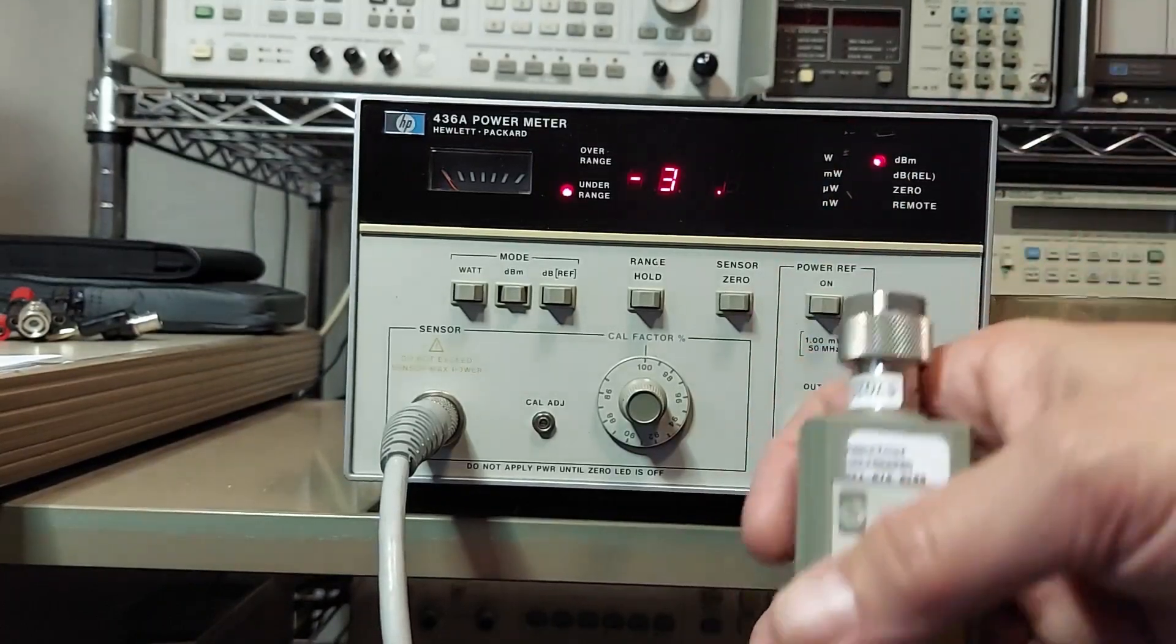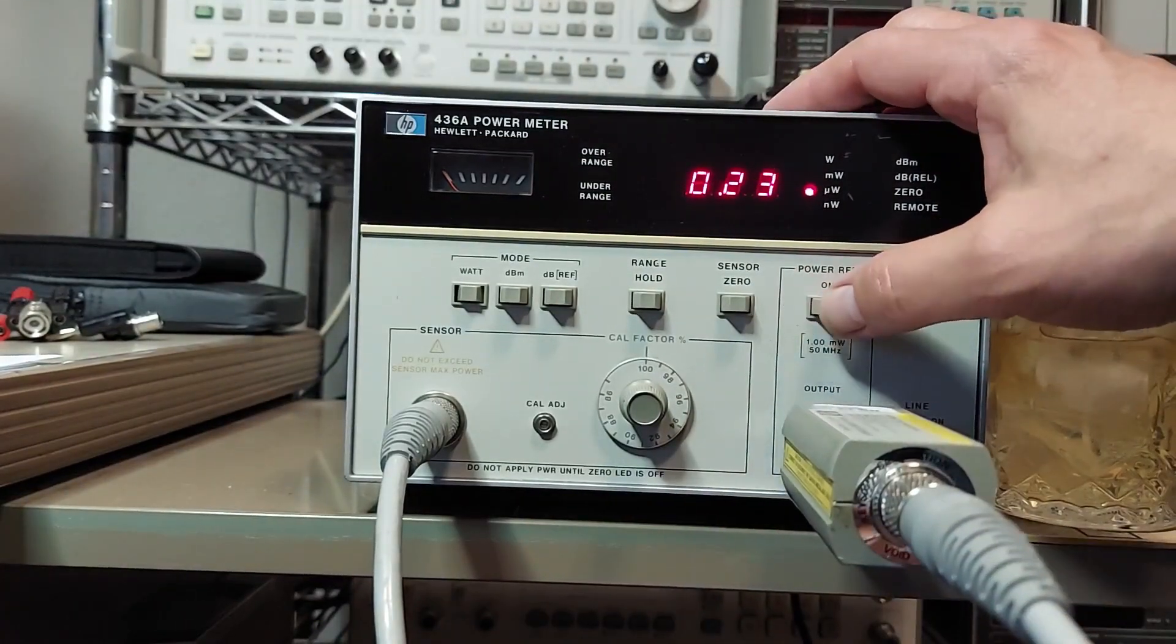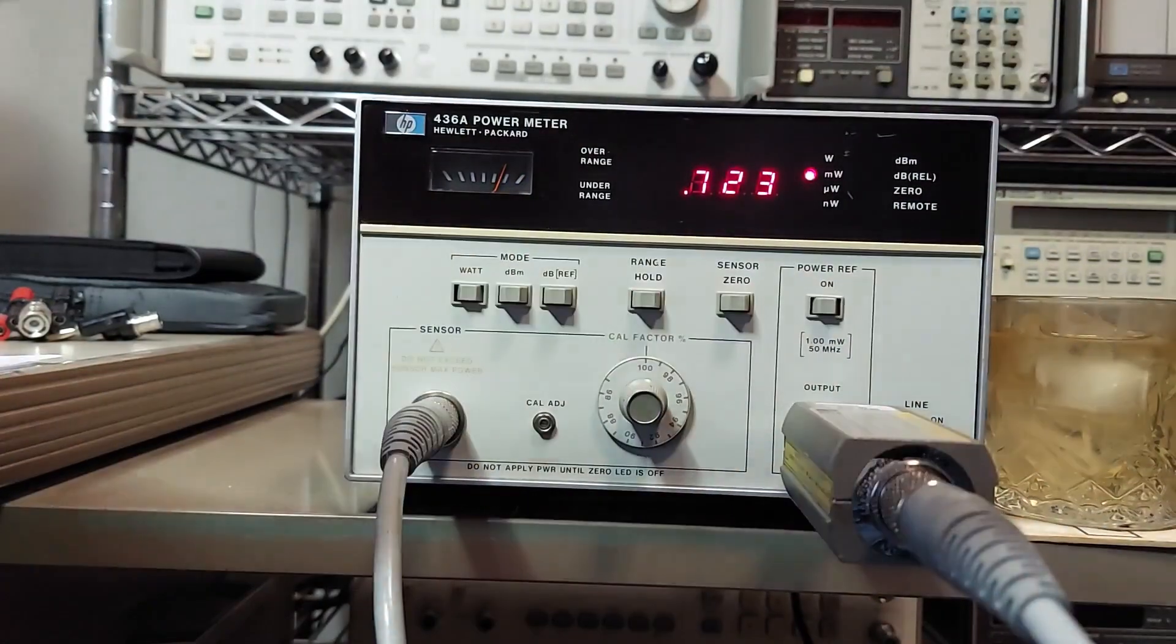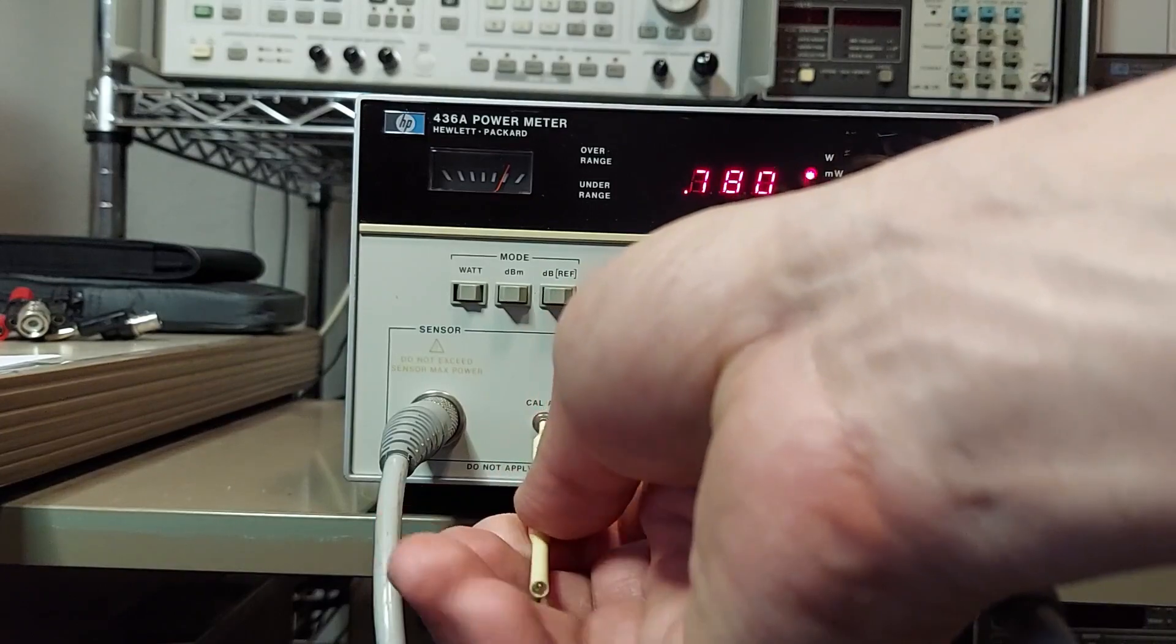Okay, the instrument's done zeroing. So now we'll take this and we'll put it into the 1 milliwatt position. And now we will hook the sensor up to our reference, and now we turn the reference on. And now what you got to do is take your golden screwdriver and you adjust this calibration control until you get one milliwatt.